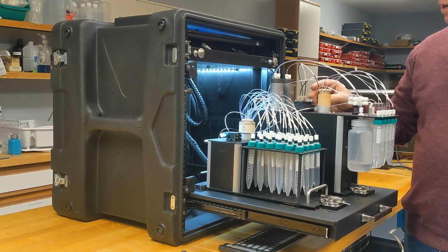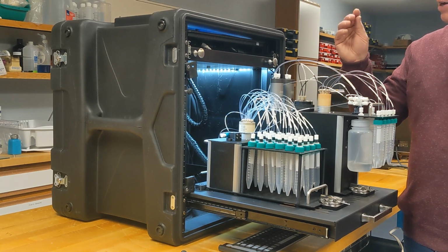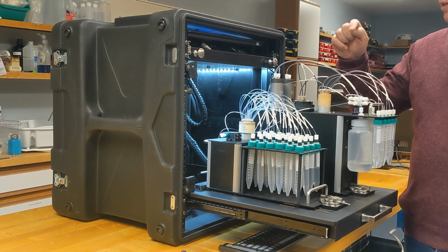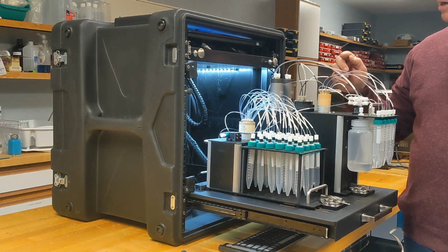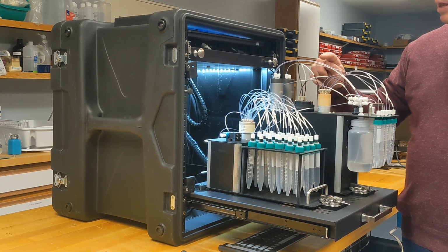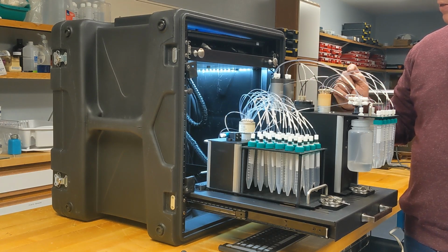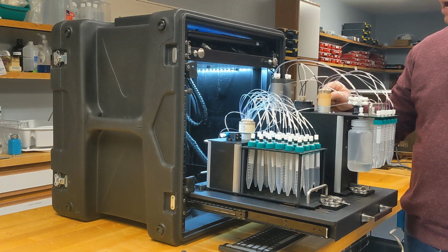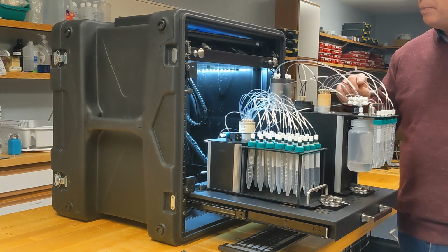This consists of a photon counter, which is monitoring the underside of a spiral channel, and that spiral channel is preceded by a merging point where the luminol comes into the detector, and the stack containing all of the reagents and the sample comes into the detector. They mix in the eye of the detector, are carried through that spiral, and then out to waste.